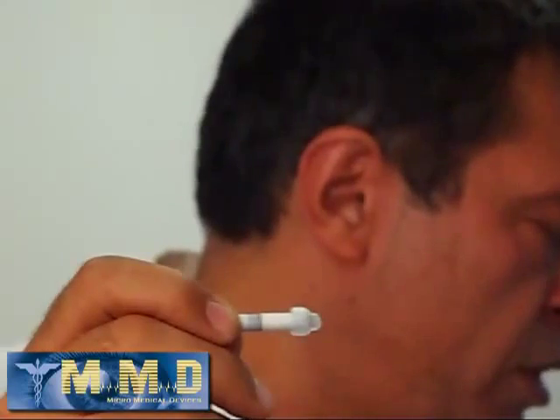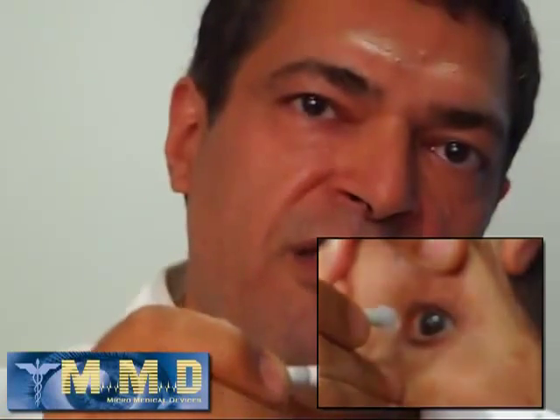The other thing I do to make sure that the patient is fixating properly, if you noticed earlier, is I ask the patient to look at the blinking light, and I move the probe back and forth and make sure that the patient is following the probe properly. That way I know that they're looking directly at the blinking light as I approach the cornea. And your approach should be very gentle, just so that the meniscus and the eye couple together, and you should have very good immersion captures with high accuracy.